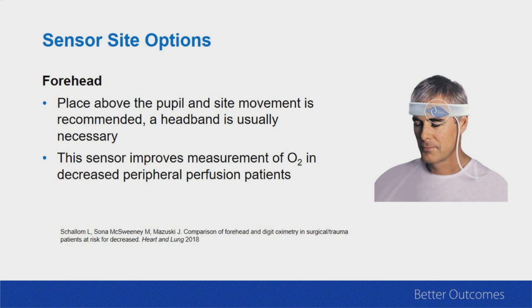Do not place this forehead sensor underneath that strap, because we generally make that strap pretty tight to help hold in that endo tube. And if you put the pulse ox sensor underneath it, you're going to create a wound. So you don't want to do that. Now, the other thing you need to do, specifically emphasized on the forehead sensor, is you need to move it on a regular basis so that you don't create the pressure wound that you can get.